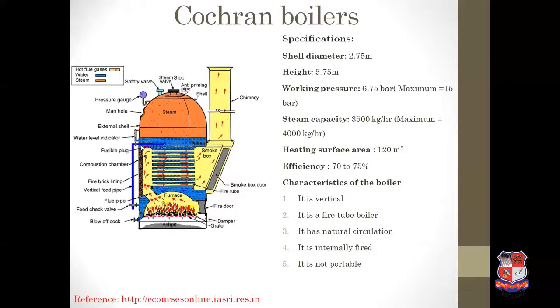There is a combustion chamber. On one side of the combustion chamber, a fire brick lining is provided, and on the other side, multiple fire tubes are provided. When hot gases come to the combustion chamber, due to the fire brick lining there is a deflection of hot gases, and because of this deflection, hot gases pass through the fire tubes. After passing through the fire tubes, they come to the smoke box, and from the smoke box, waste gases go to the chimney and into the atmosphere.